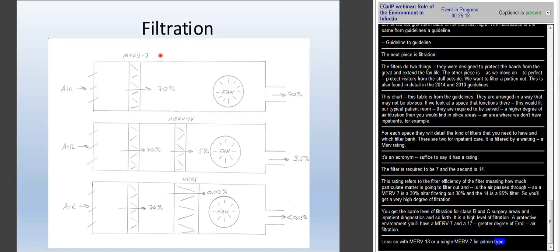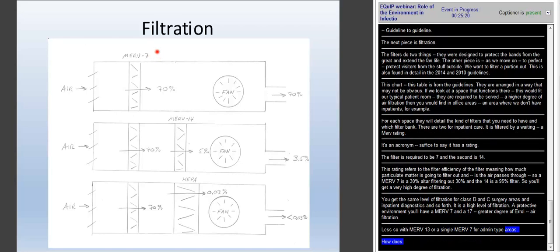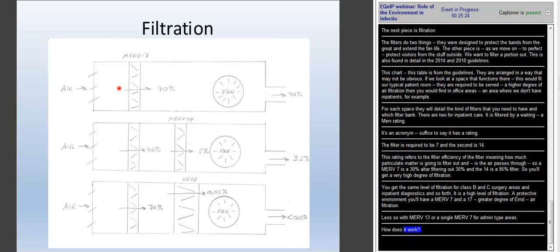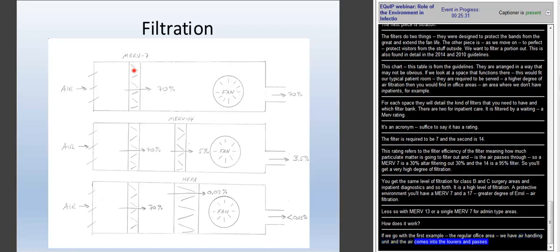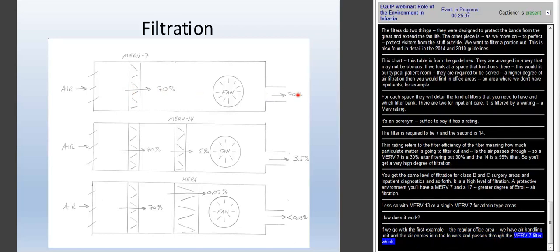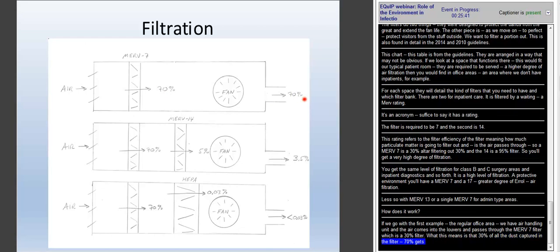If we go with the first example being a regular office area, we have our air handling unit. The air comes in through the louvers. It passes through the MERV 7 filter, which is a 30% filter. And so what this means for us is that 30% of all the dust is captured here in the filter, but 70% of that gets through, and we're delivering 70% of that dust downstream. Okay? So none of these filters are perfect. They do not take out all of the dust.